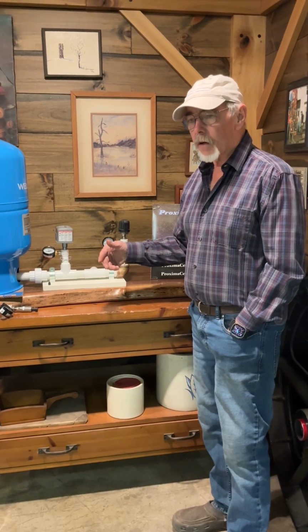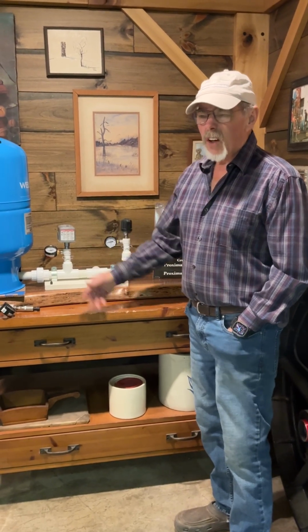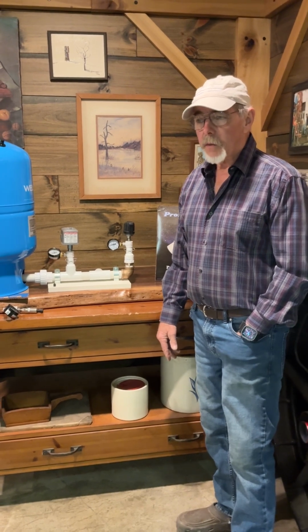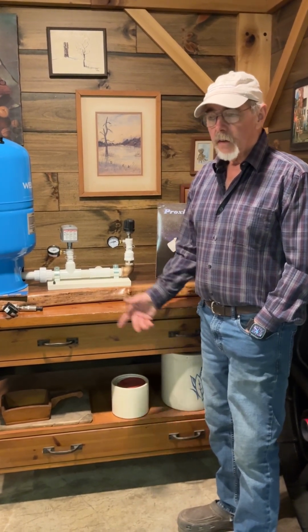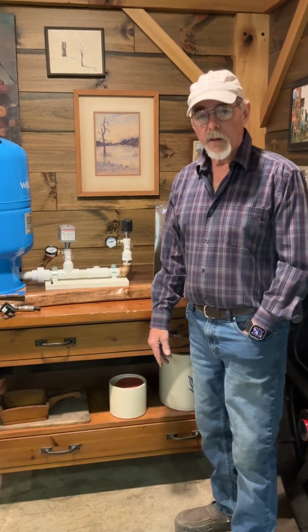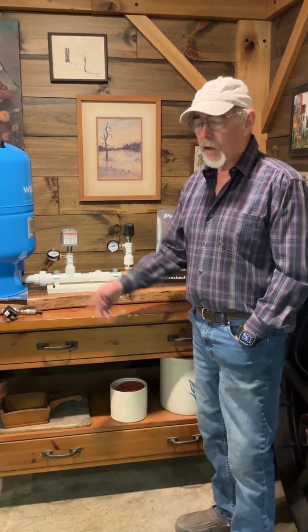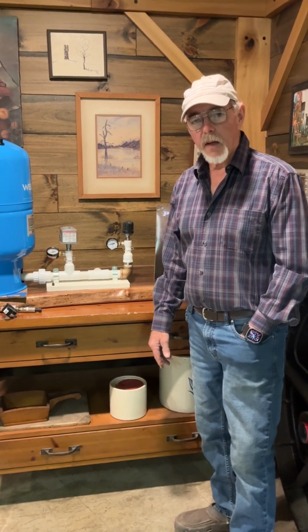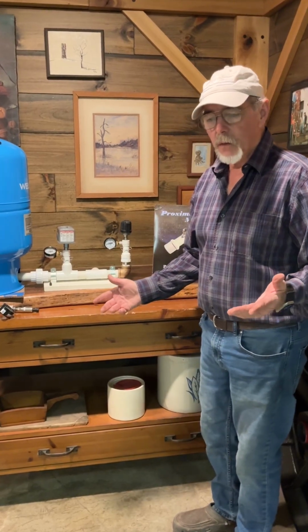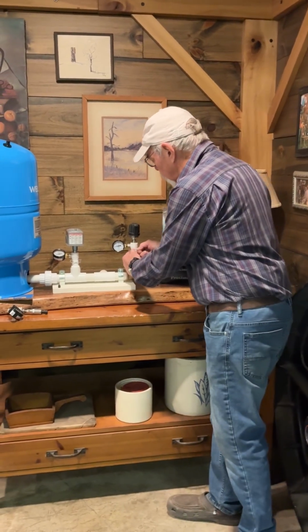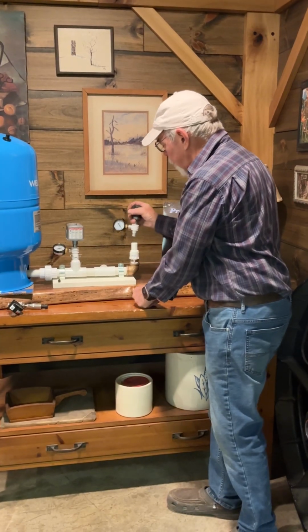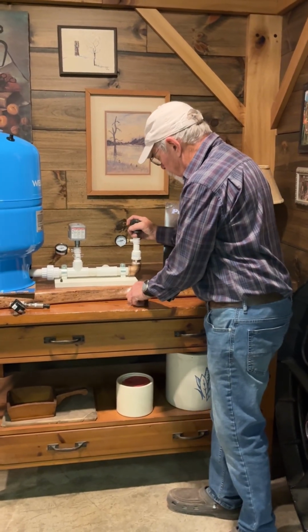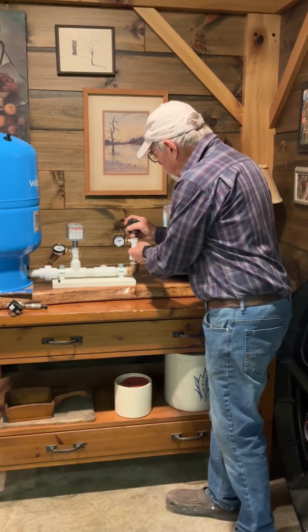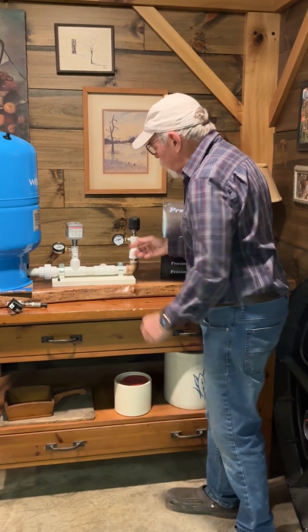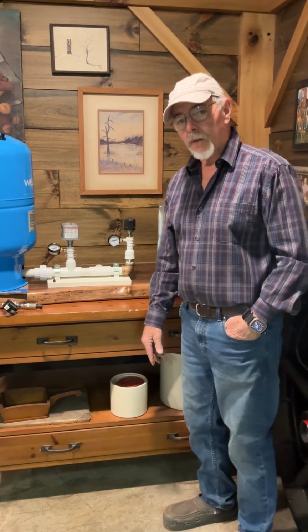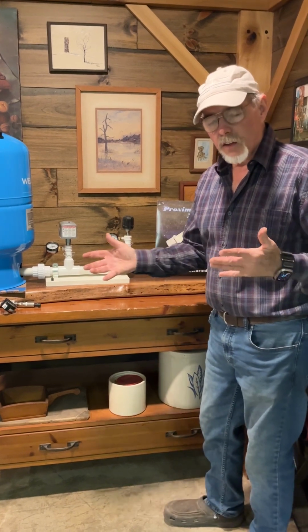They talk about a customer calling up and saying, my gauge is reading 30 PSI, and you go out there and you don't really want to drain the whole system down for that, because you put the gauge on 3 months ago and now they want you to come back and change the gauge. It happens, we all know that. You can just go out there, unclip that, pop that loose, change that gauge, put it back in, and you help the guy out. He's happy, he's got a new gauge on there, and you didn't even have to mess around with too much of anything. You just got her done that easy. That's quick.